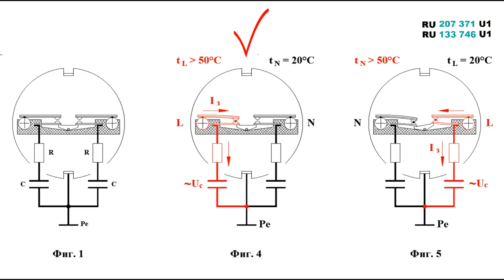The middle figure shows the situation when the phase conductor connection overheats. The corresponding overheating of the bimetallic contact leads to a short circuit to the ground through the current limiting RC circuit. The parts conducting the current are highlighted in red. Reaction to the short circuit will be disconnection of the protection device and termination of the power supply.